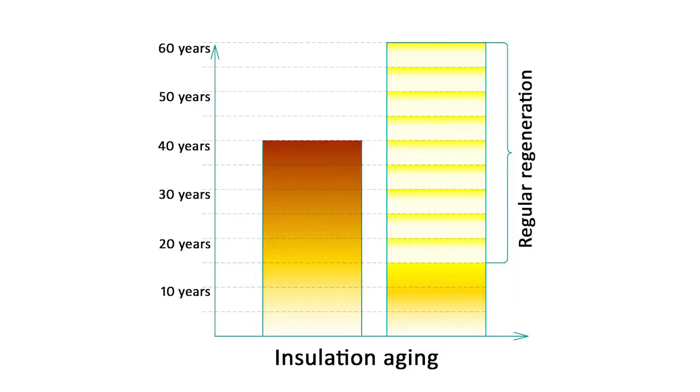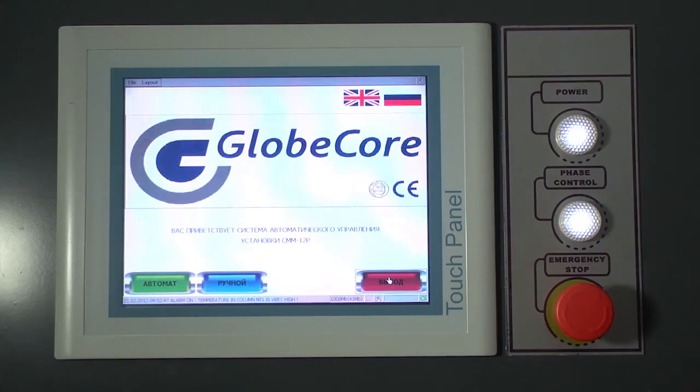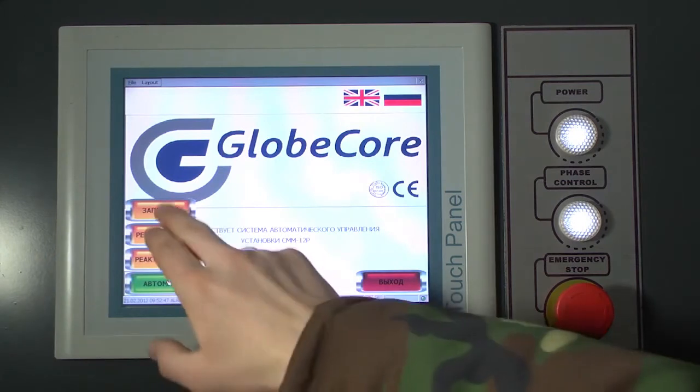Fuller's earth can be reactivated up to 300 times. Reactivation restores absorption ability of the media. Sorbent is reactivated within the machine. No unloading is required. The reactivation process is safe and has significantly lower energy costs. Treatment is fully automated. Operator participation is minimal.